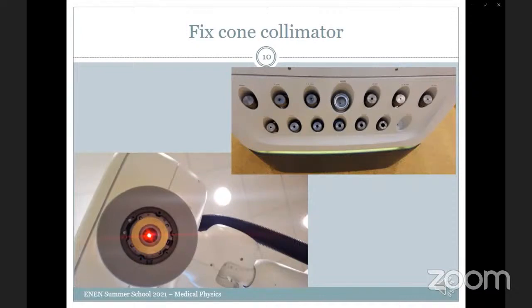The disadvantage of this collimator is that it needs much more time for treatment because it can only deliver circle-shaped beams, so we cannot use irregularly shaped fields. So you have to use many more beams and many more directions, and we have to go inside the treatment room during the treatment to change the collimators.